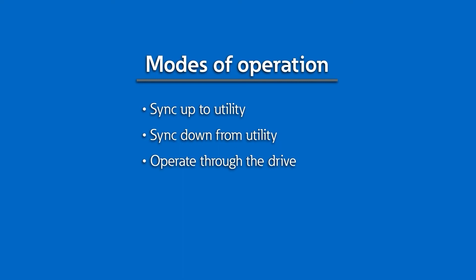The system then opens the VFD output contactor and finally the motor select contactor to accomplish the closed transition. Once synchronization is complete, the drive is now available to perform one of three tasks: sync up a motor to the utility bus, sync down a motor from the utility bus, or operate the motor through the drive.